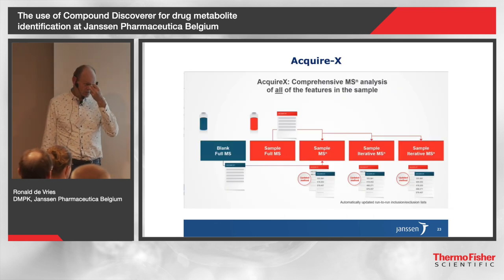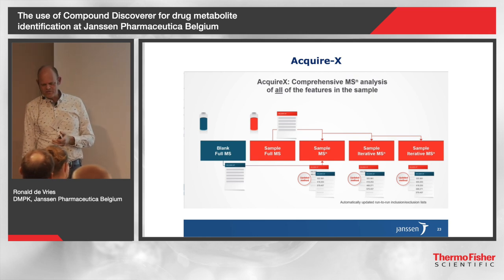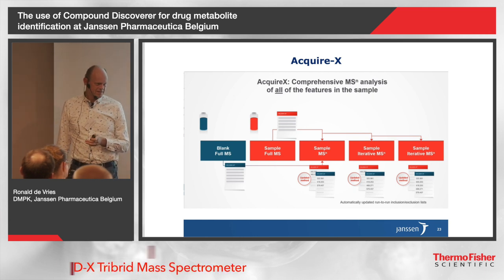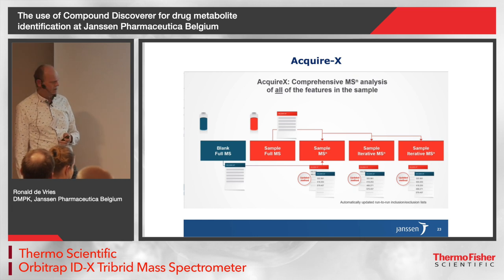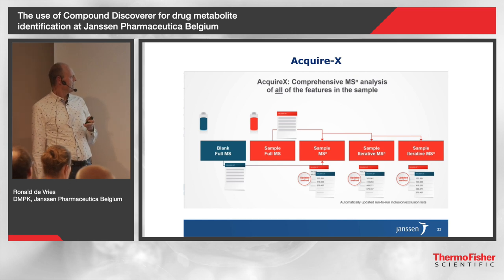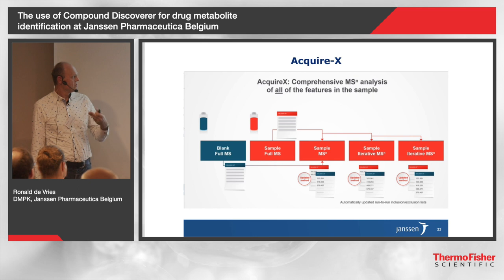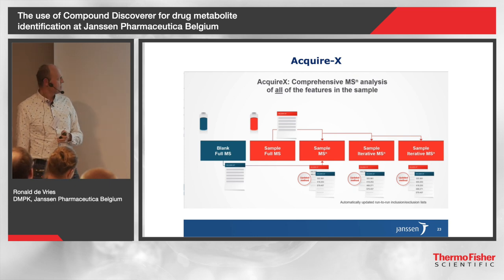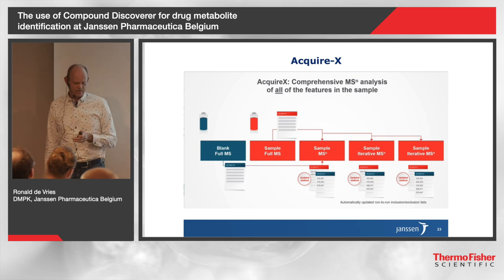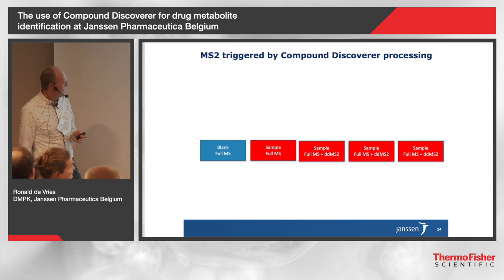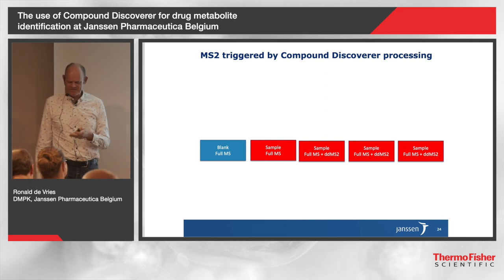At ASMS 2018 we got AcquireX. So if you buy a nice new tribrid Orbitrap IDX, I think it comes with AcquireX, which is really neat. What it does — for people who haven't seen this yet — is it injects a blank sample and the actual sample. From the blank it generates an exclusion list, and from the sample an inclusion list. Then based on these lists, it does MSN with a new injection. Every MSN that has triggered is put on an exclusion list, and re-injections are done until all the hits on the inclusion list have been covered. Only one disadvantage: not available for Q Exactive, at least not yet — maybe for Christmas.